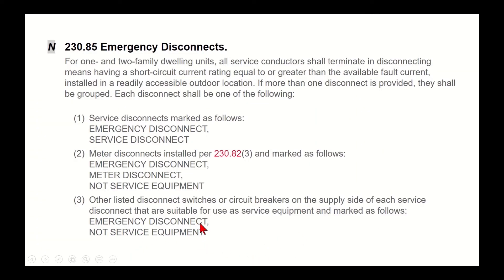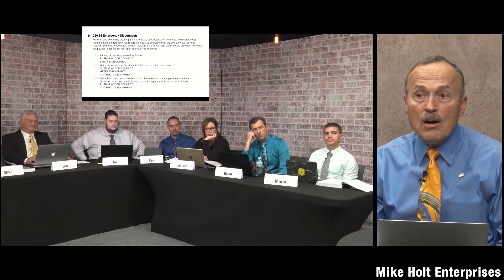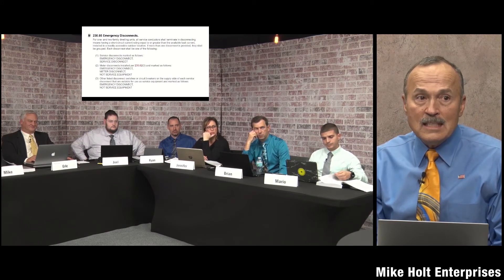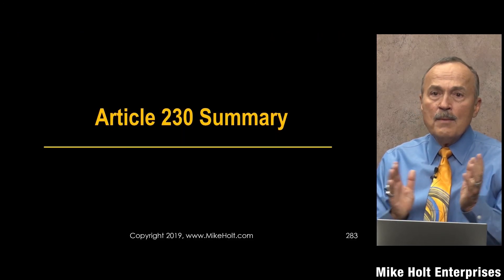This is an emergency disconnect — not a service disconnect — that is after the meter on a service change, so that the service disconnect located indoors is still marked service disconnect. But even though this is a disconnect rated for service equipment, we're going to have a bonding and grounding problem. Section 250.25 added requirements on how to bond and ground disconnecting means located ahead of the service disconnecting means.